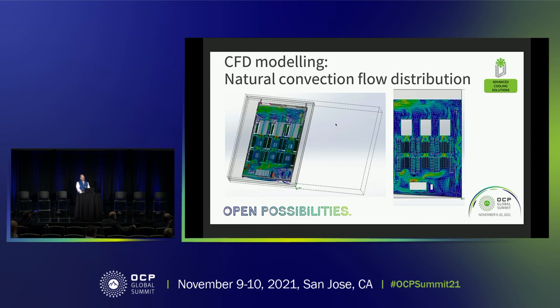Each of the servers, the 3 servers shown on the screen, are each getting a good flow, and you can see that on the image on the right. There is an attraction of flow to the heatsink, you can see on the bottom left, and a good attraction on the others too. The central server does seem to not be getting quite as much cooling, but actually when we look at the thermal results, you'll see that each of the servers is cooled adequately well. At the top of the screen, you can see the exit flow.